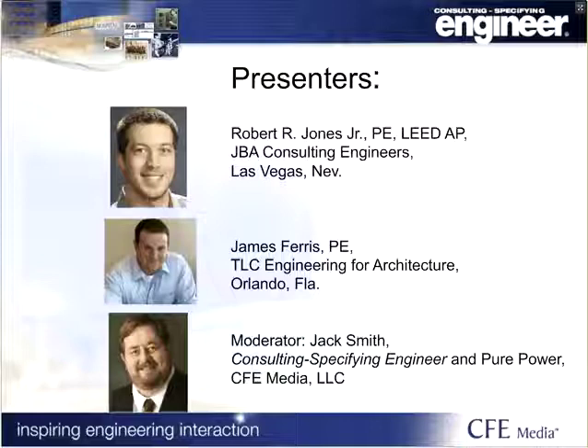Thanks. Rob, here's a long question for you: describe the proper percentage load that is best for a diesel generator over an extended period, based on your suggested method of consideration of standby, prime, and continuous ratings. In other words, does specifying prime rating versus standby rating increase the longevity of the generator?